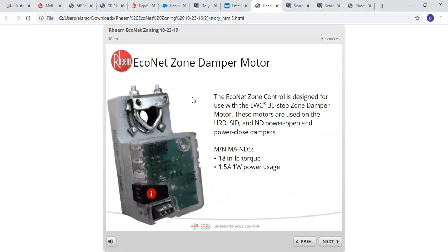This is one of the Econet zone damper motors. They're again made by EWC. You have your 3 terminals here: common, power open, power closed. And you do have a manual gear release. So if you push this button, you can release the gear to adjust the damper. The Econet zone control is designed for use with the EWC. They have 35 steps in their zone damper motors. These motors are used on the URD, SID, and ND power open and power closed dampers.